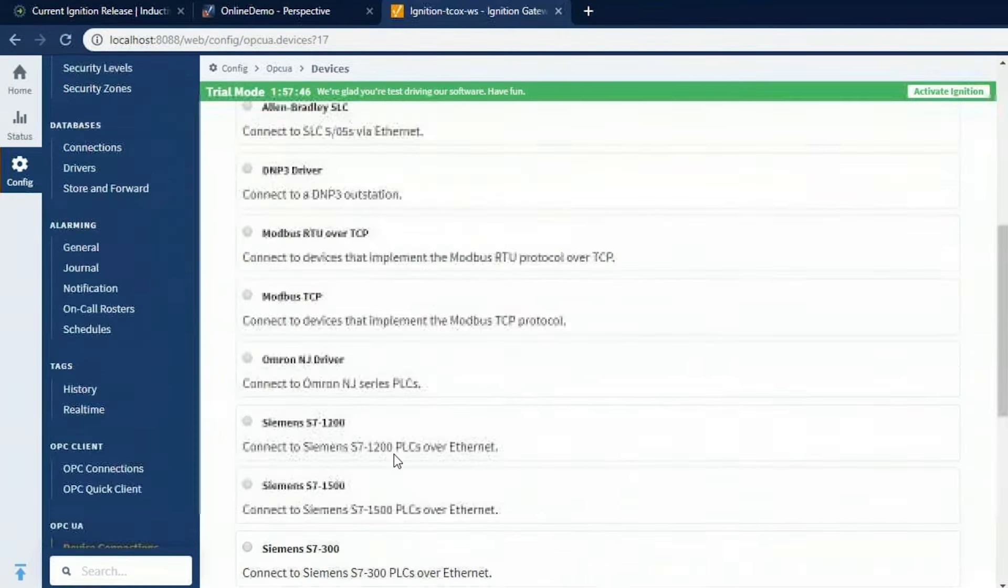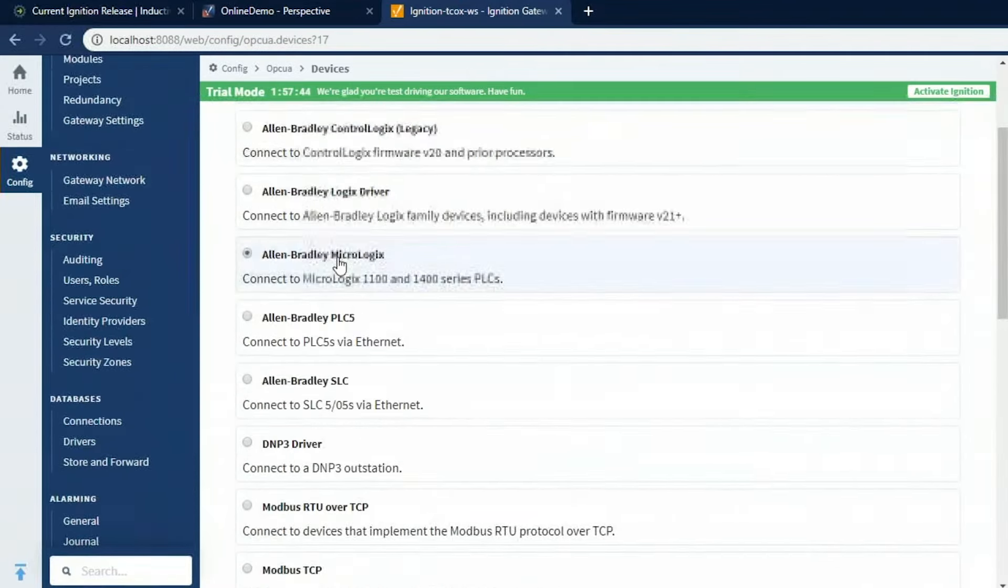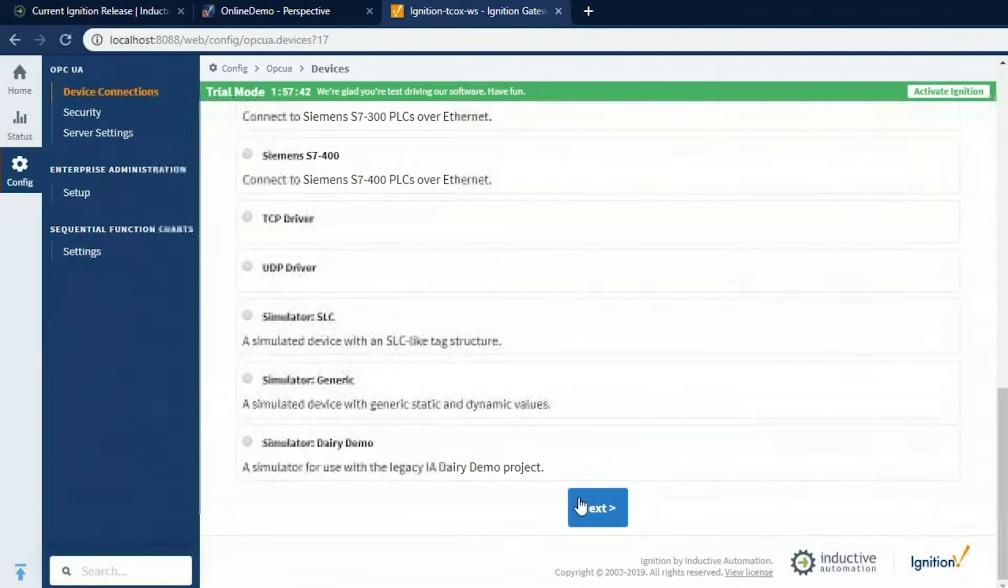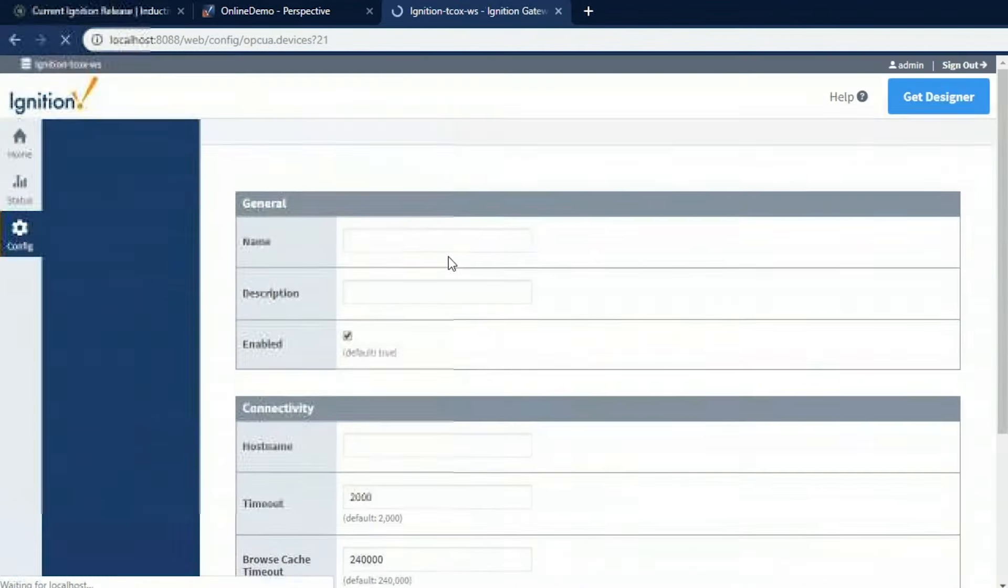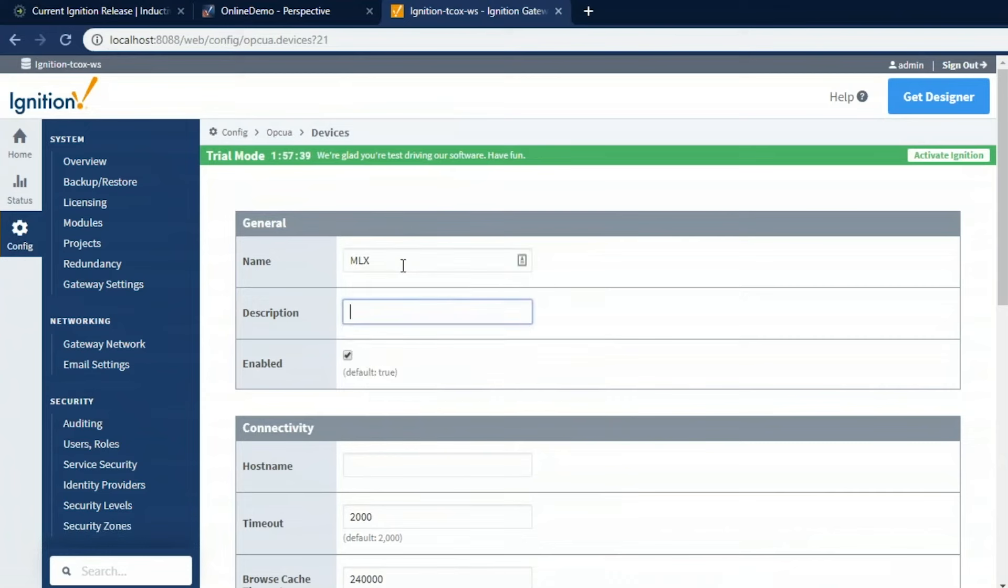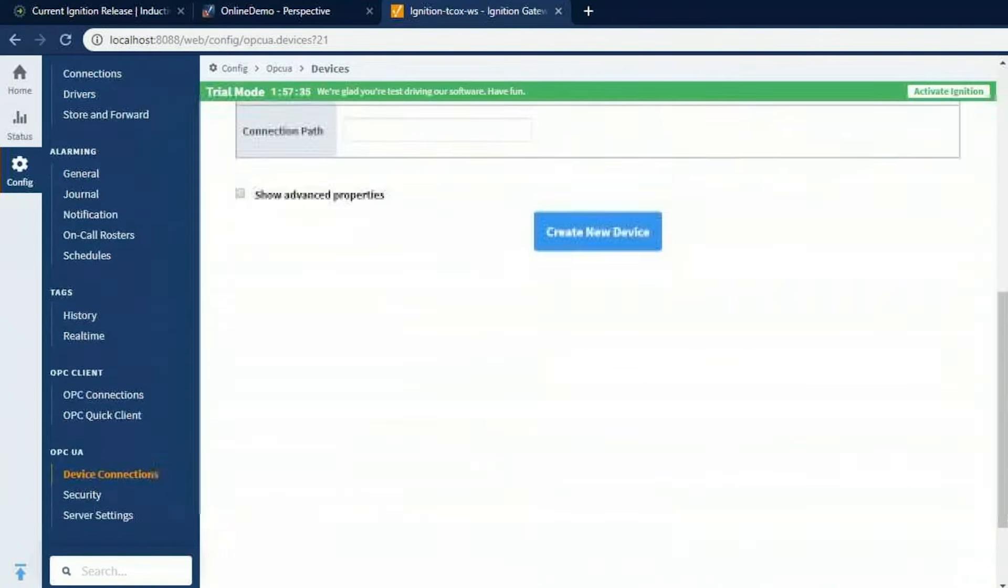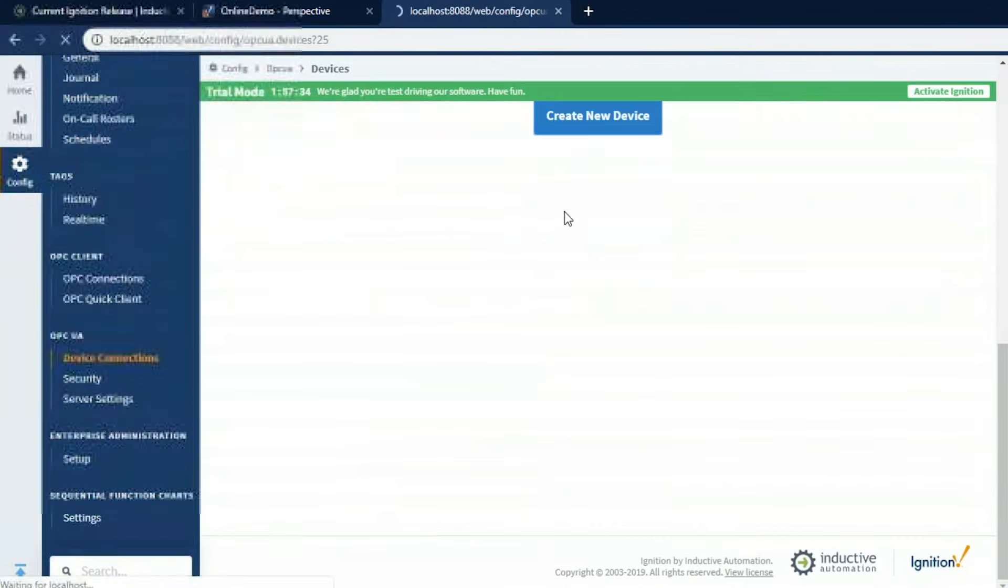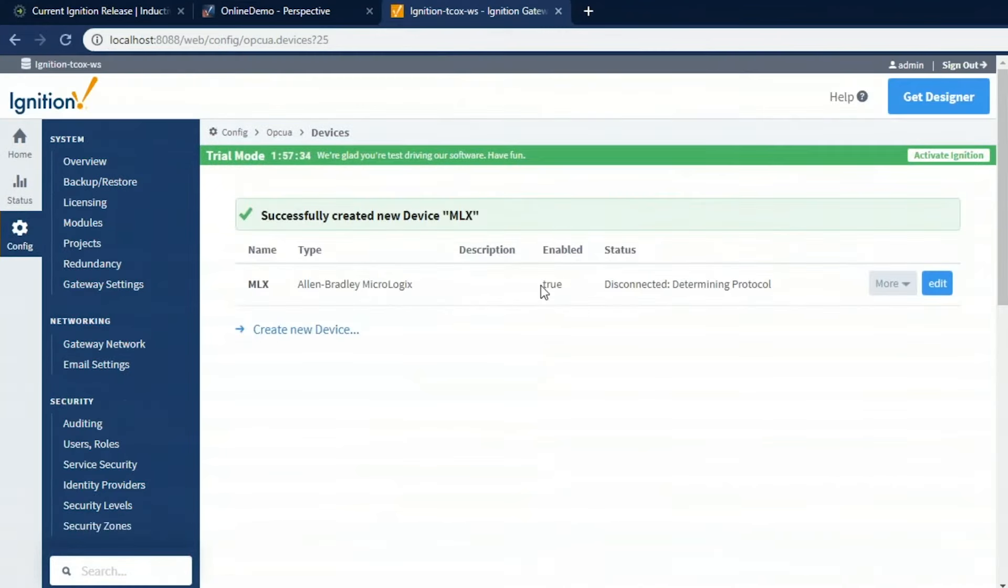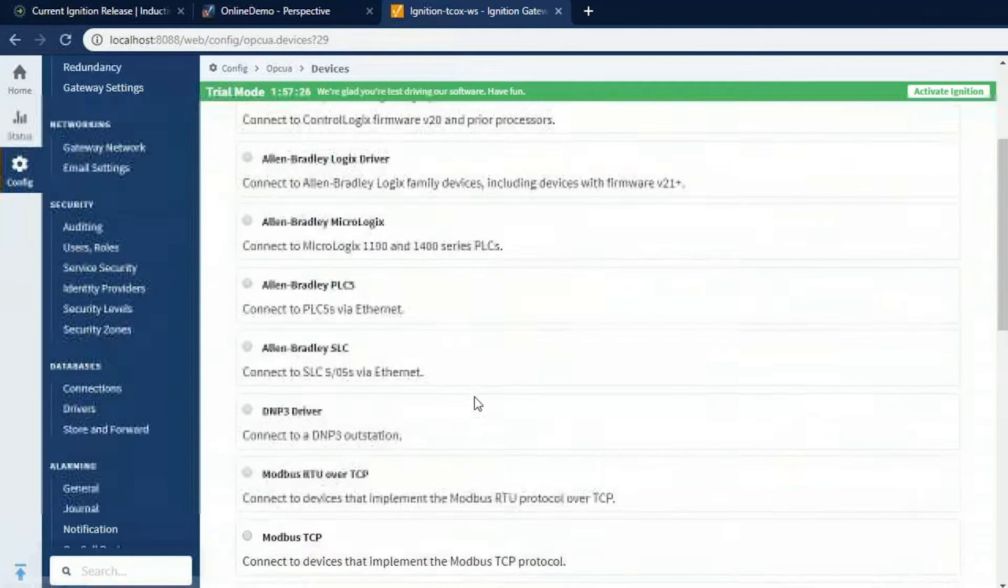So let's connect up to two different PLCs. Let's do a MicroLogix, go next. I'm going to call this one MLX and put the IP address 10-20-7-77, come down here and create the device. As you'll see here, it'll go from disconnected to connected. So now we're ready to go. We can start reading information from that PLC.